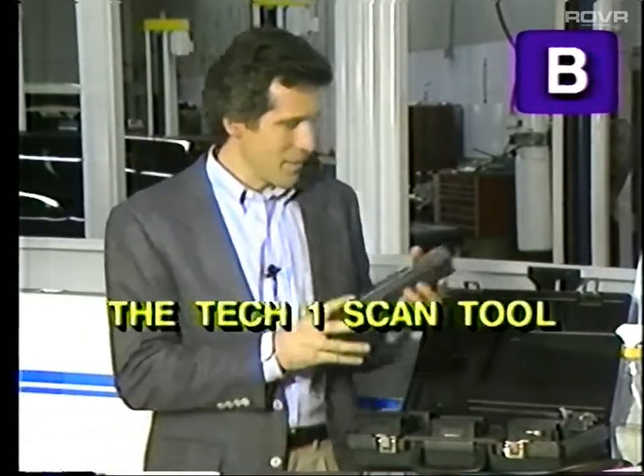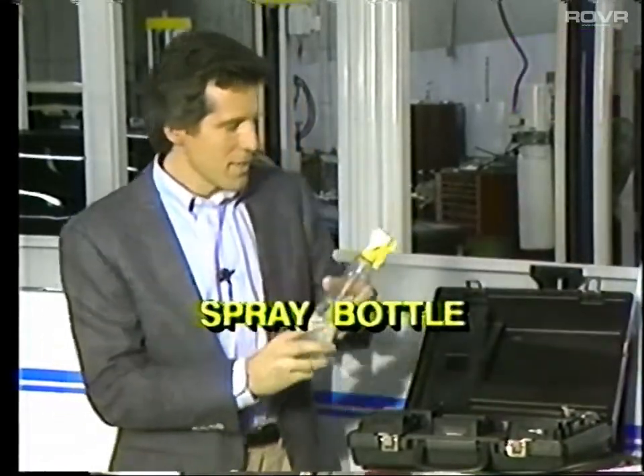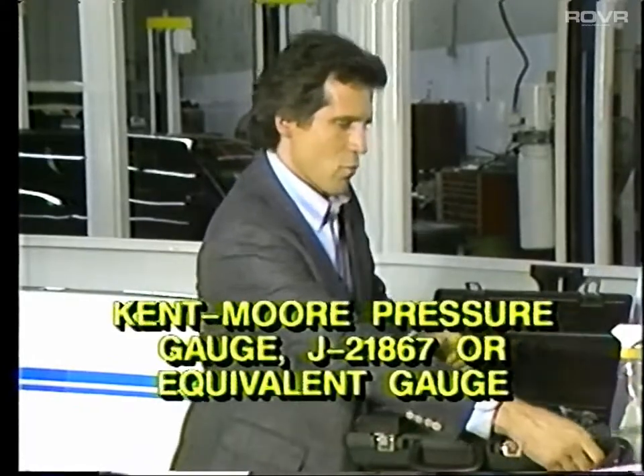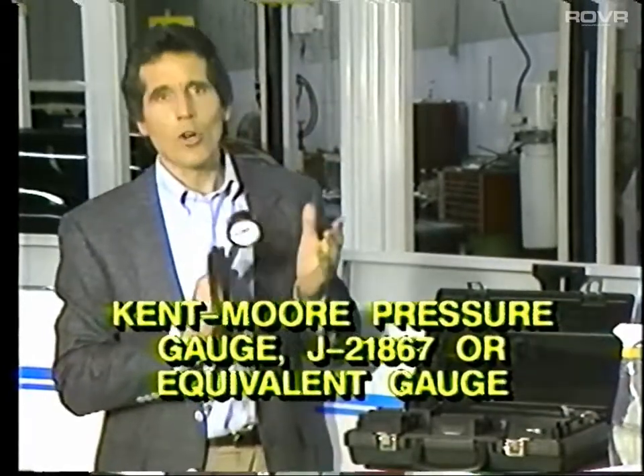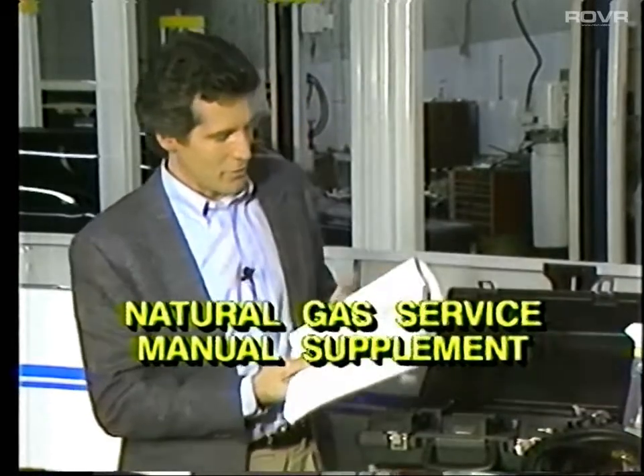Now, here are the tools that you'll need. Tech 1 scan tool, a spray bottle, a Kent-Moore pressure gauge J21867, or an equivalent gauge capable of reading pressures up to 250 psi or 1380 kPa. And don't forget the natural gas service manual supplement. These natural gas systems are new to you, so use this manual. It'll save you a lot of time.